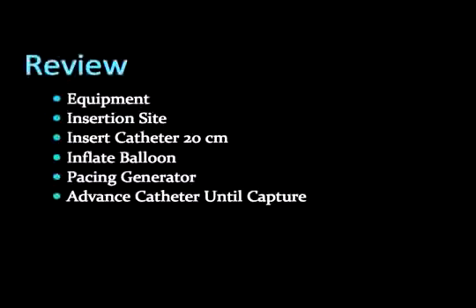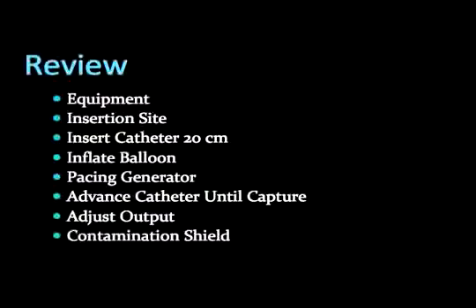Advance the pacing wire until capture occurs. Decrease output to a minimum level to sustain capture. Then slightly dial back up to a comfortable level above this threshold. Lock the contamination shield in place. Secure the catheter firmly in place via sutures.